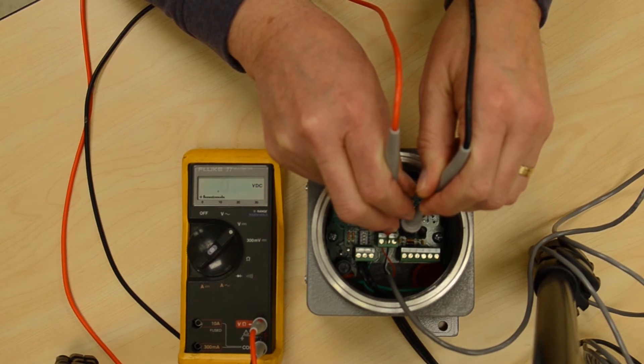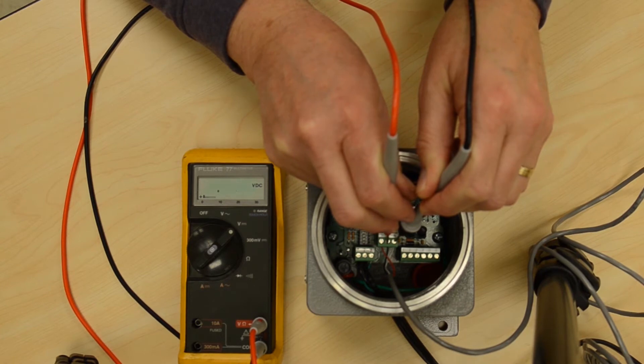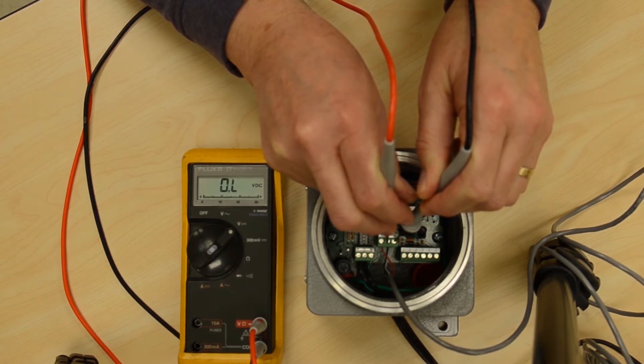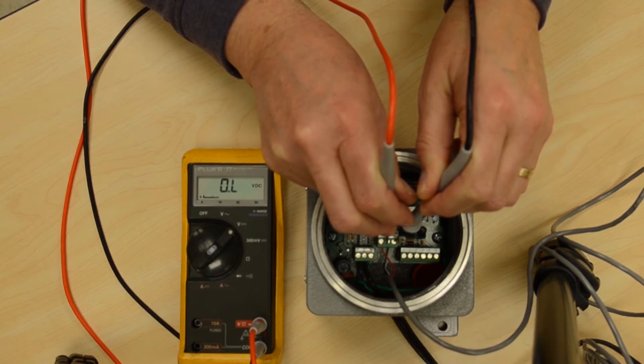If the sensor is running on a slow speed shaft, you will see pulses on the voltmeter. And if the sensor is running on a high-speed shaft, over 50 rpm, the readout will be approximately half of the power supply.